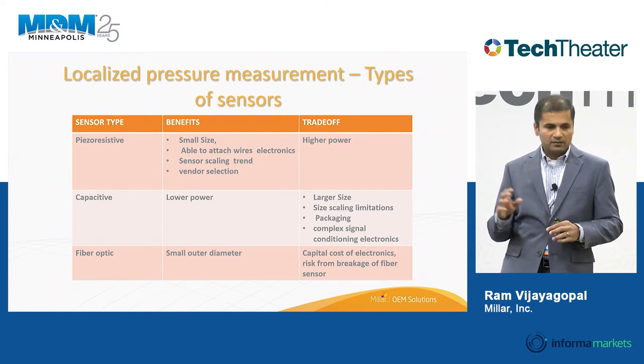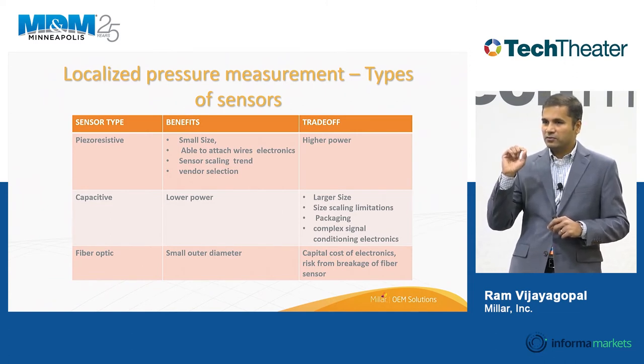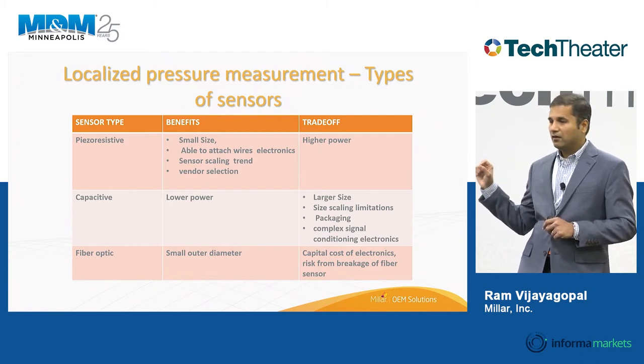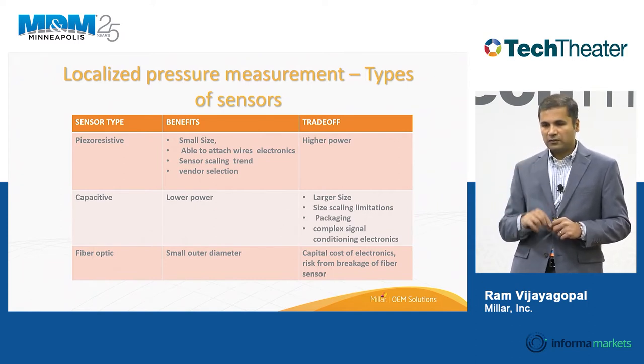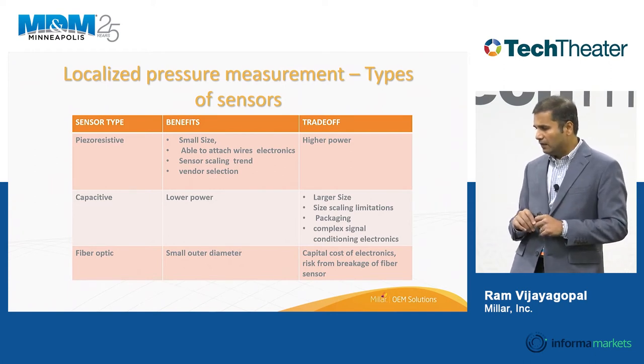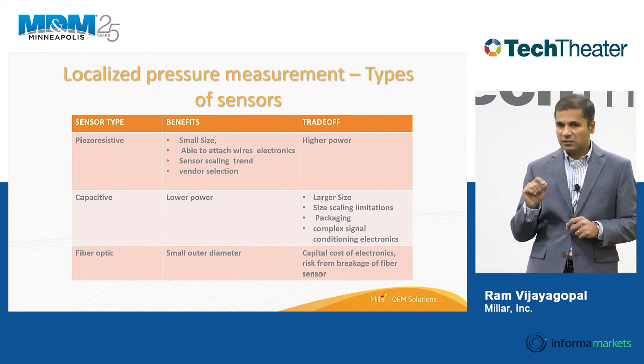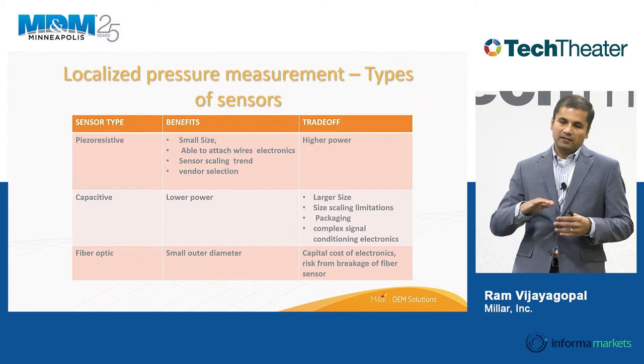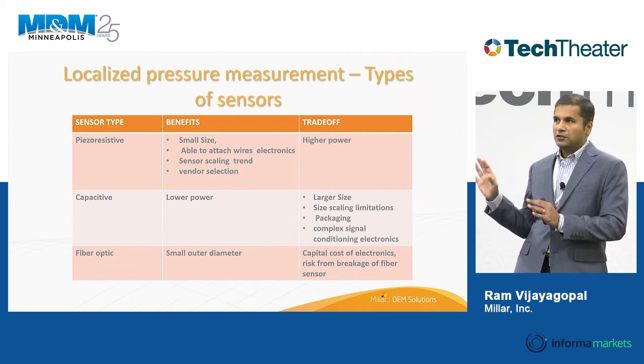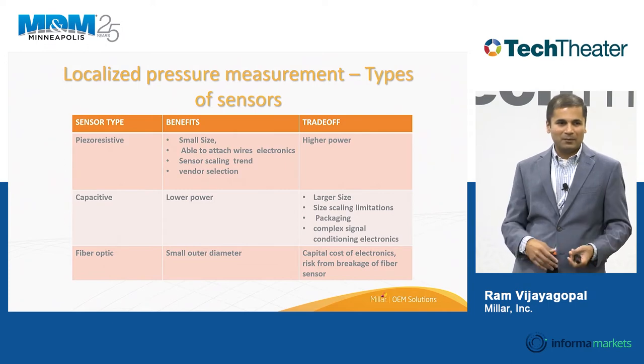The third category is fiber optic sensors, typically found in applications measuring pressure through very fine or tortuous vasculature, such as FFR applications where a guide wire or fiber optic cable is threaded to a fine portion of the vasculature. However, fiber optic sensors are very fragile and prone to breakage. They're also susceptible to drift as the patient rolls over or the fiber bends, though companies have evolved techniques to mitigate that.